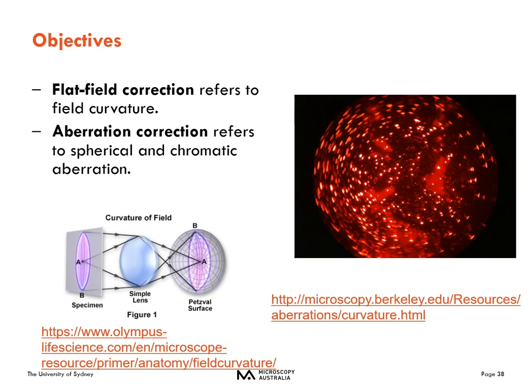Field curvature means you get a sharp focus at the center of your field of view but blurring toward the edges — a fishbowl effect — unless extra lenses flatten it out. This is what we mean by flat field or flat field correction. Unless you're only looking at the very center of your image, you really want to use a plan objective.